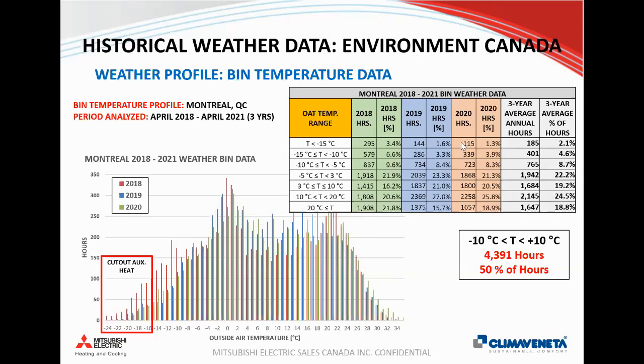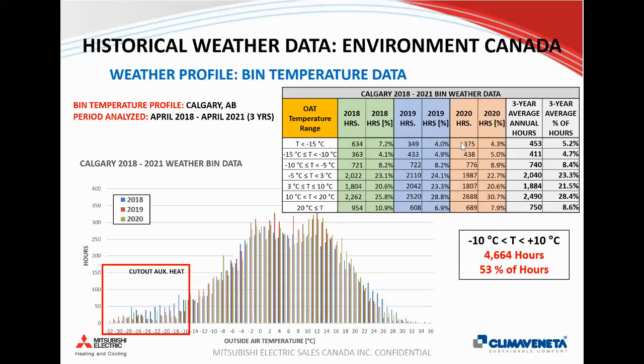And this is why I show this data, because whenever you look at the actual number of hours, you'll see that it's not necessarily as big of a deal, and you can overcome this, for any designers in the room, by just having an auxiliary heat source. So again, even in Calgary, it gets very cold, below -30, and you do see more hours that are spent below -15 in the Calgary climate. But again, between -10 and +10, there's still over 4,600 hours, 53% of the time, that you're spending within that temperature range.